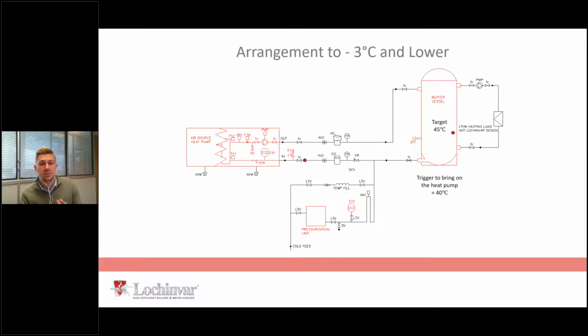And because the buffer vessel is basically going to be a tall, skinny vessel, if you flow out and flow back and you want to create a broader delta T for your oversized radiators, or it's an underfloor heating loop and you want a big delta T, you want to flow out at 45 and come back at, I don't know, 20, something like that, just put a slower flow rate in.